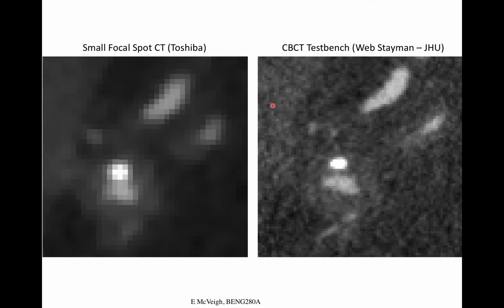So it's the statistics of sampling, and it turns out that the generation of the X-rays goes as a statistical process, which is governed by a Poisson distribution. And the detection of the X-rays is also a statistical process that's a Poisson distribution. So if I try to generate 10,000 X-rays with my X-ray tube, and I set everything up perfectly, my mA and everything, I say, okay, that should give me 10,000 X-rays coming out of there. And I go, bam! You'll get 10,000 plus or minus every time, right? Because the process itself isn't deterministic. It's a statistical process.